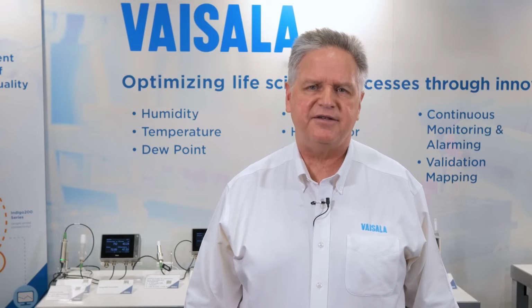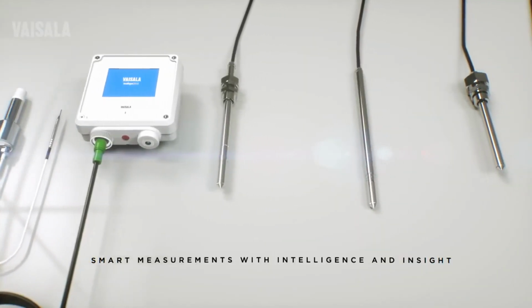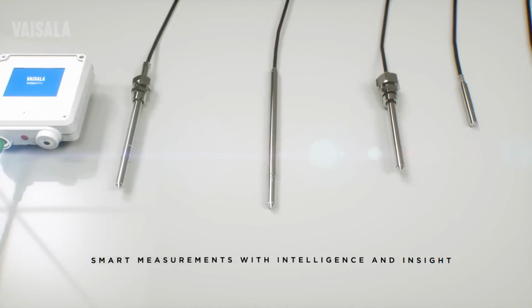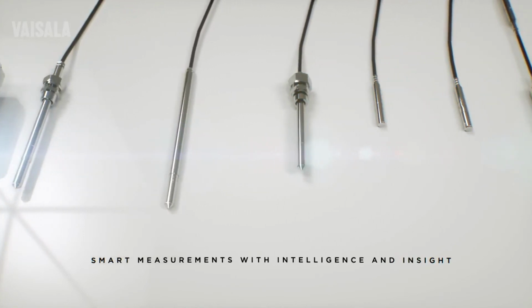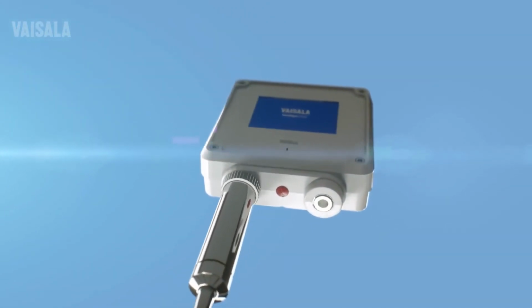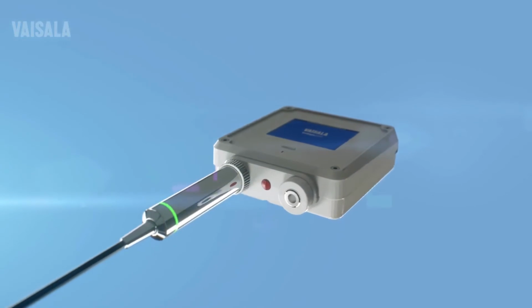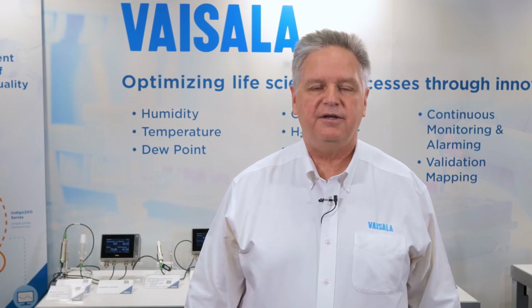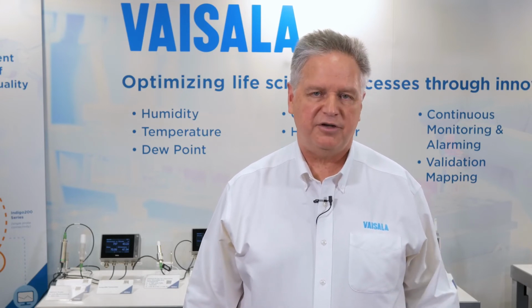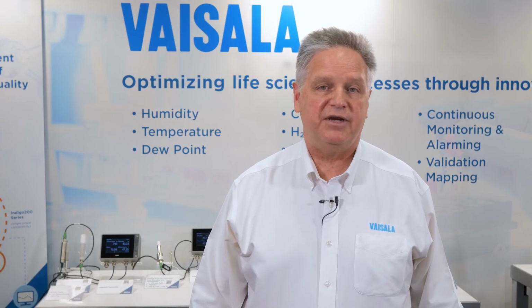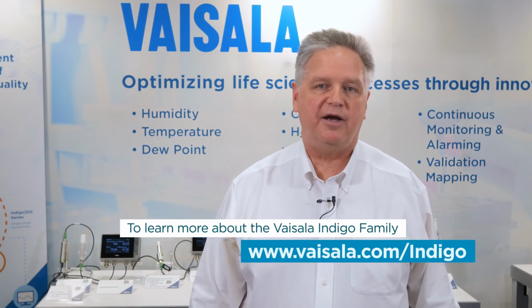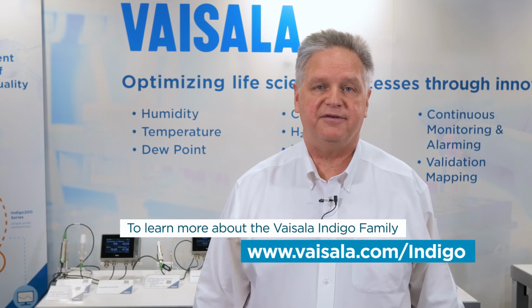One of our latest sensing technologies we've developed is a sensor that measures vaporized hydrogen peroxide. It's a common agent used to biodecontaminate. So in between processes and testing, you need to make sure that the space you're working in is free of any previous cells that might have been grown. And this gas, vaporized hydrogen peroxide, is ideal for destroying all of those cells that are there. And we have a sensor that can measure the relative humidity, the concentration of the vaporized hydrogen peroxide, the temperature of the process, and also the relative saturation of the process, allowing you to measure all the required parameters to make sure you're decontaminating the process to meet the requirements in that application.